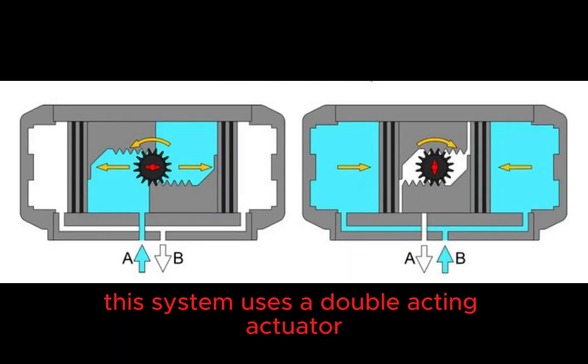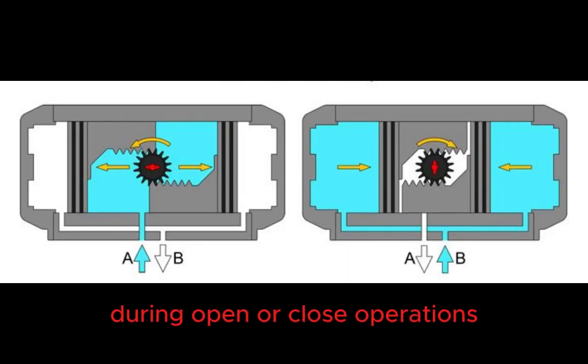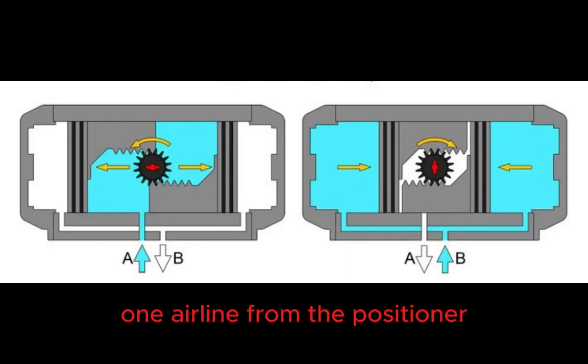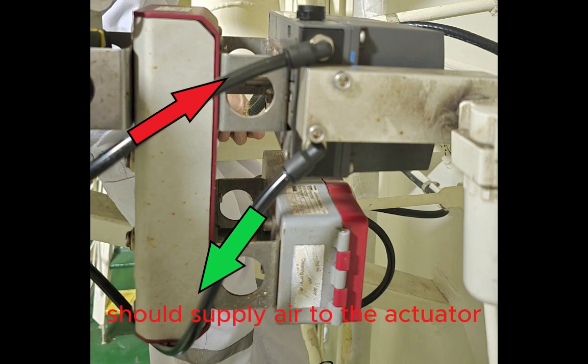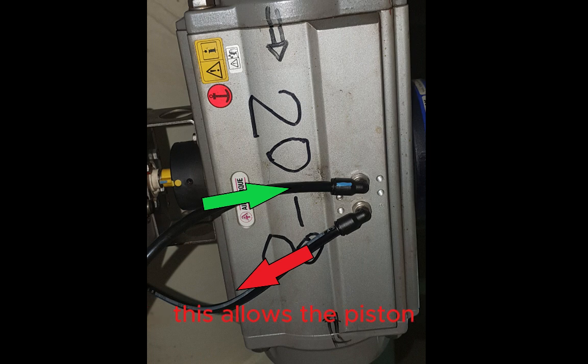This system uses a double-acting actuator. During open or close operations, one airline from the positioner should supply air to the actuator, while the other should vent back. This allows the piston inside the actuator to move and operate the valve.